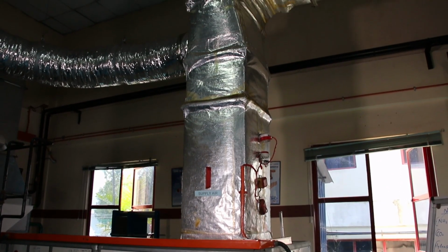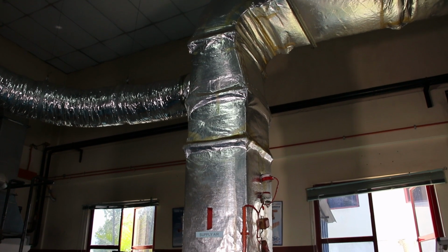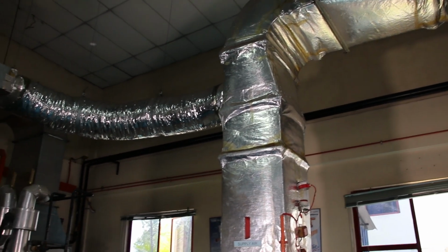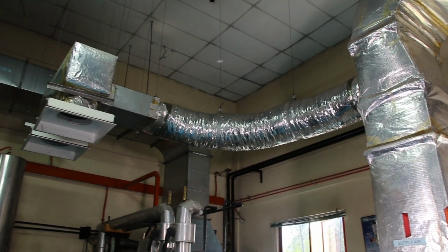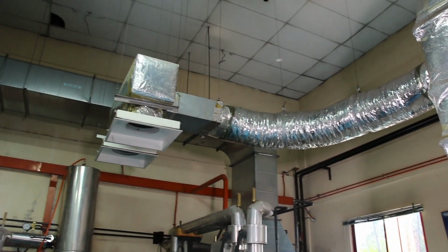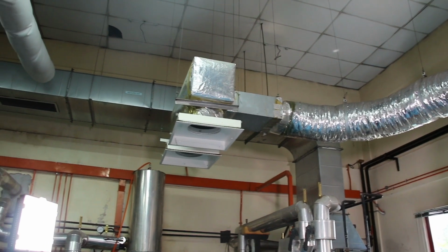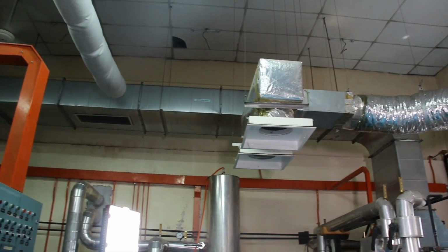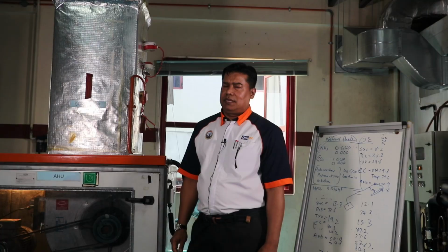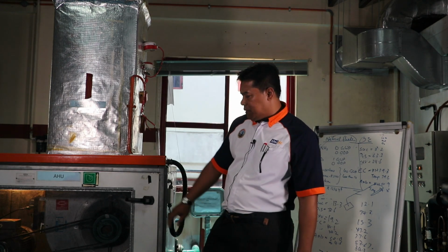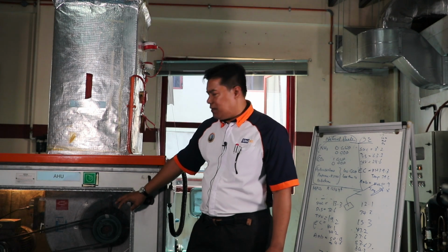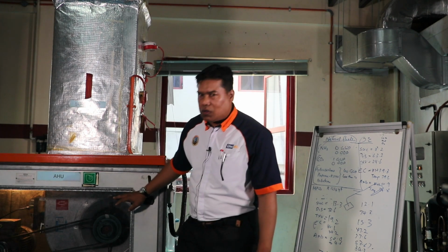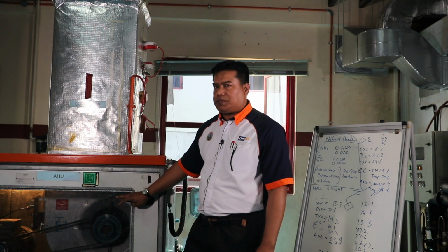In this topic, students will be taught to measure the air flow and its distribution in a duct using given equations. The Blasius and Colebrook equations are applied in calculating the pressure drop of a duct. The second outcome is to determine the performance and sizing of the fan using the Rateau coefficient and the fan laws.